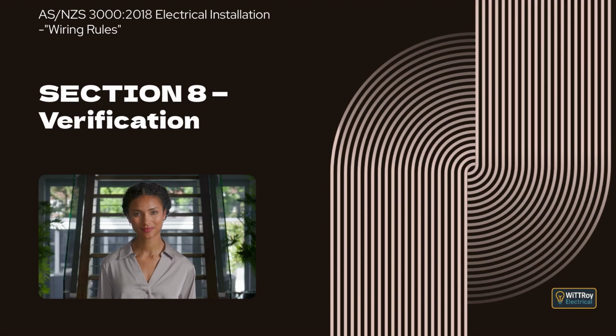The clause then covers earthing. The inspection checks the main connection, the earth electrode, and earthing conductors for correct size and identification. Equipotential bonding conductors are checked for size and identification, along with connections, joints, and terminations. Protection against external influences is confirmed, and connections to earthing arrangements for other systems are reviewed. The inspection also considers whether the creation of an earth situation may require additional earthing of electrical equipment.